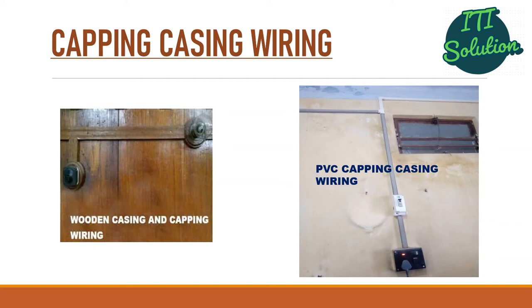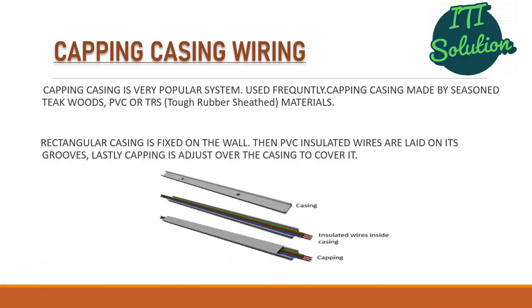Now we discuss about capping casing wiring. This is the wooden capping casing wiring and this is the PVC capping casing wiring. Capping casing is a very popular system used frequently. Capping casing is made by seasoned teak wood, PVC, or TRS — tough rubber sheathed materials. A rectangular casing is fixed on the wall, then PVC insulated wires are laid in the grooves, and lastly capping is adjusted over the casing to cover it.